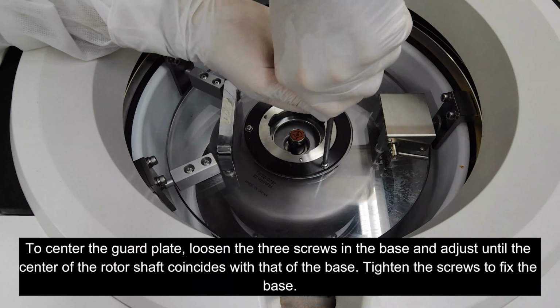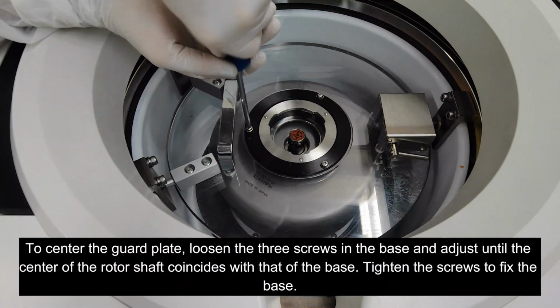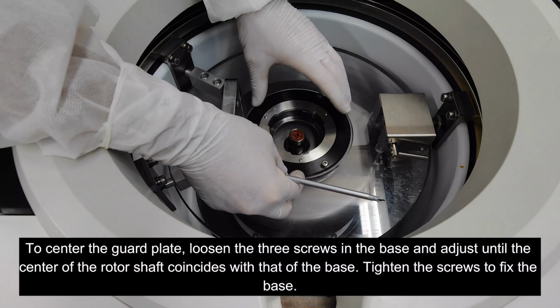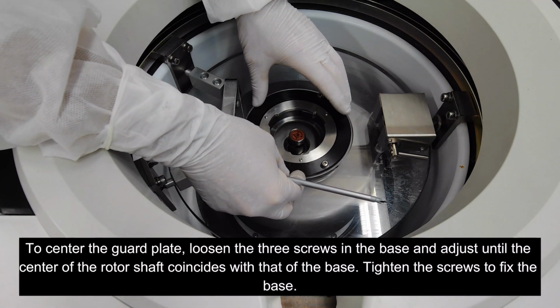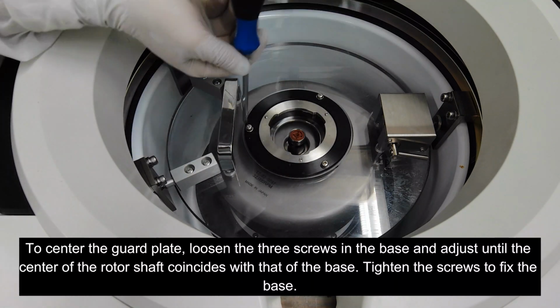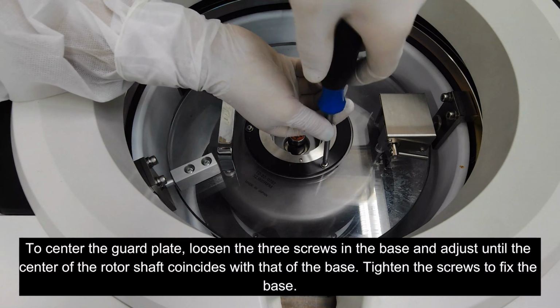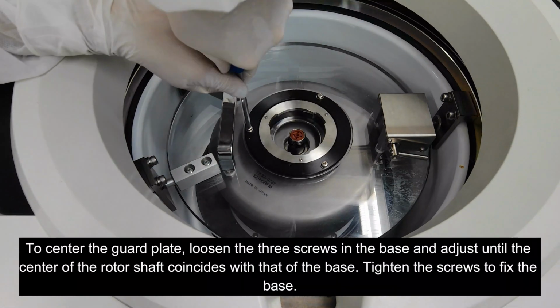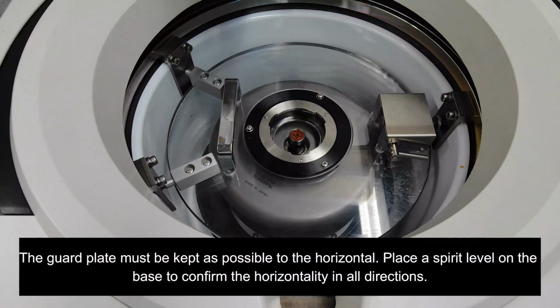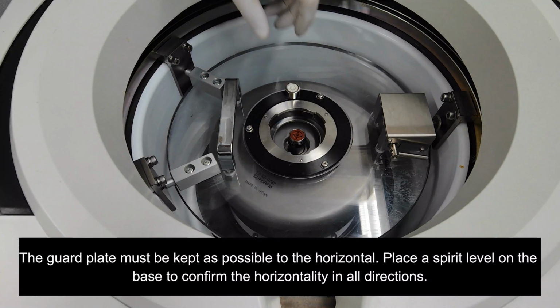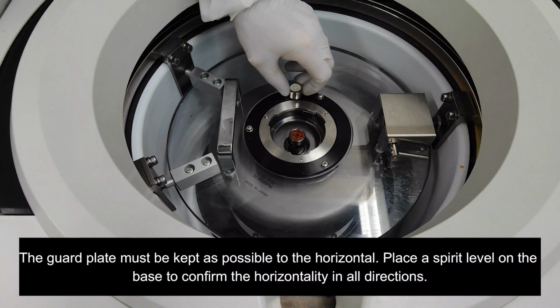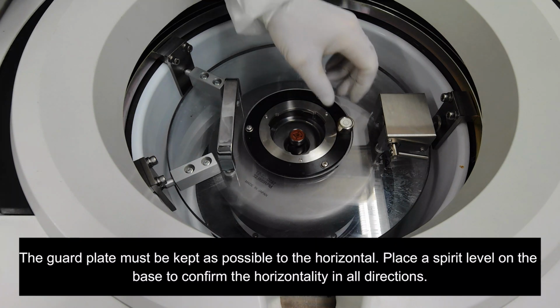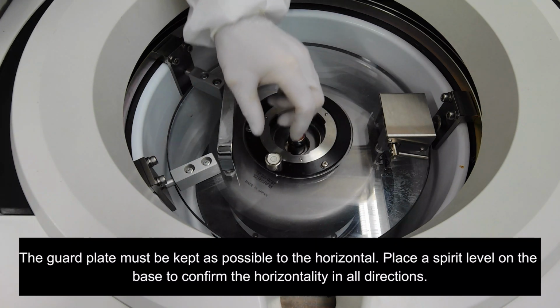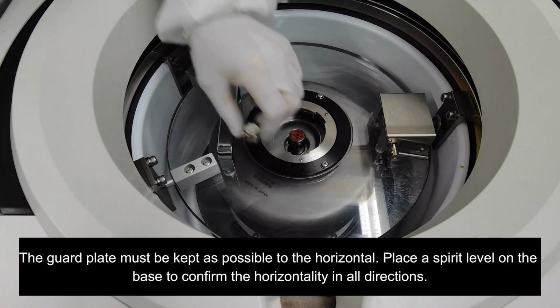To center the guard plate, loosen the 3 screws in the base and adjust until the center of the rotor shaft coincides with that of the base. Tighten the screws to fix the base. The guard plate must be kept as horizontal as possible. Place a spirit level on the base to confirm the horizontality in all directions.